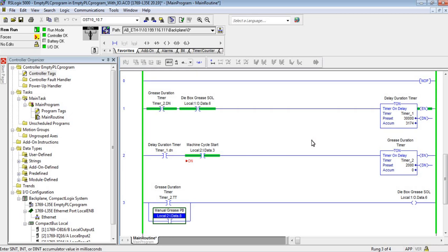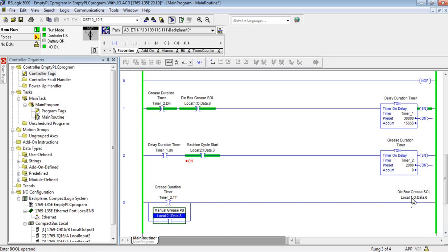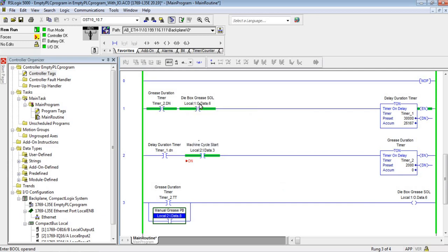Now that is a difficult thing to do comparatively with a relay-only machine, because you have to go in there and confirm you actually have contacts, normally closed contacts, on whatever is running this. You may have to add a relay just to get some normally closed contacts, or you have to see if the push button maybe has a normally closed contact.